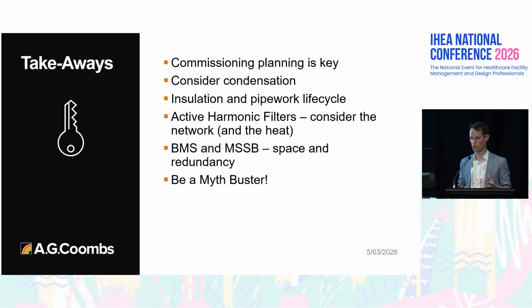Look at insulation and pipe work as a life cycle assessment as part of your assets, and make sure you're considering the insulation side of things. In most installations we go into, you can find at least a few examples where the vapour barrier has been compromised, and you've got sagging or under-insulation corrosion.